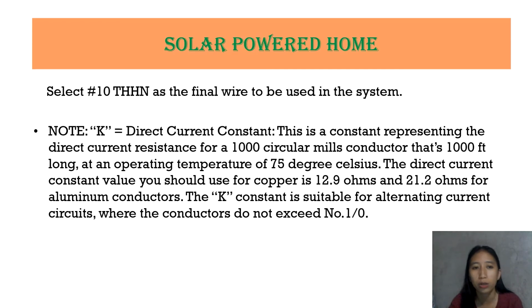Okay, so note, K is equal to the direct current constant. This is a constant representing the direct current resistance for a 1,000 circular mils conductor that is 1,000 feet long. At an operating temperature of 75 degrees Celsius, the direct current constant value you should use for copper is 12.9 ohms and 21.2 ohms for aluminum conductor. So, sabi dito, kapag copper yung gagamitin natin, dapat 12.9, and then pag aluminum conductors naman is 21.2 ohms.